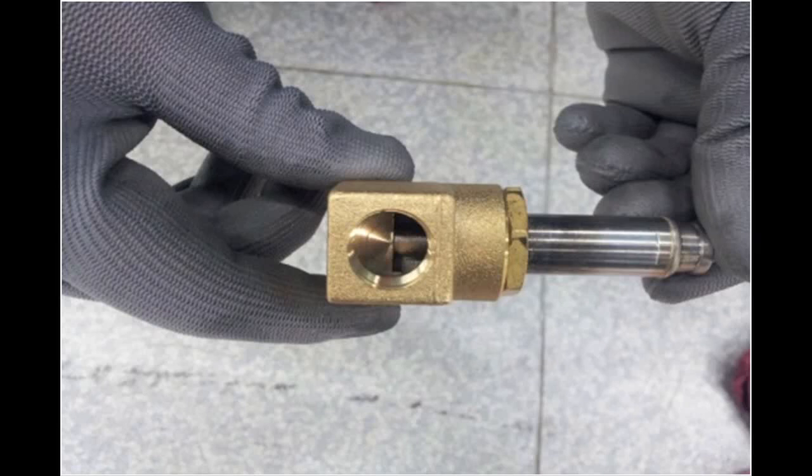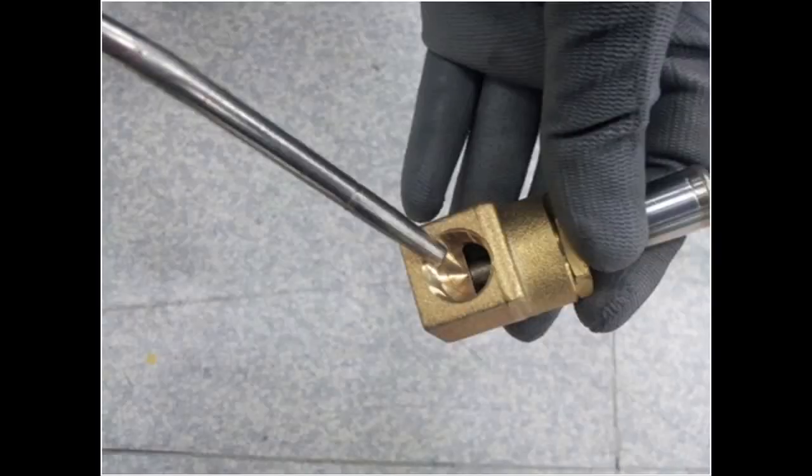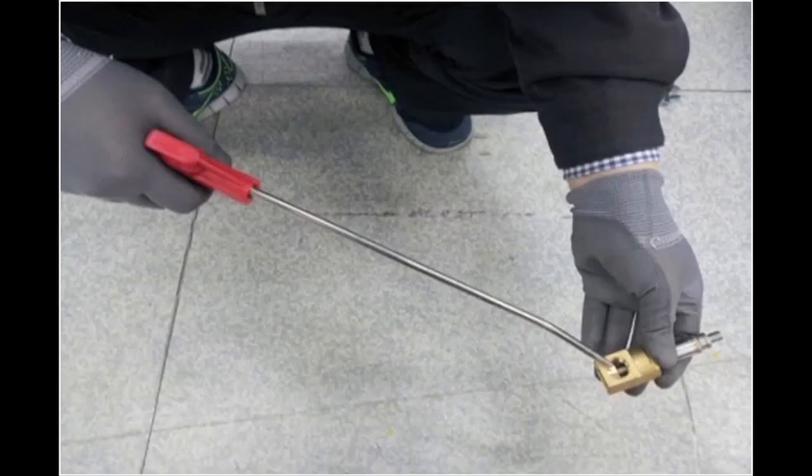Step 8. Immerse the valve in hot water, over 60, for 3 minutes and clean inside of the valve with compressed air, 4 to 7 kilograms per centimeter 2. Step 9. Reassemble the valve, following instructions in reverse order from Step 6 to Step 1.